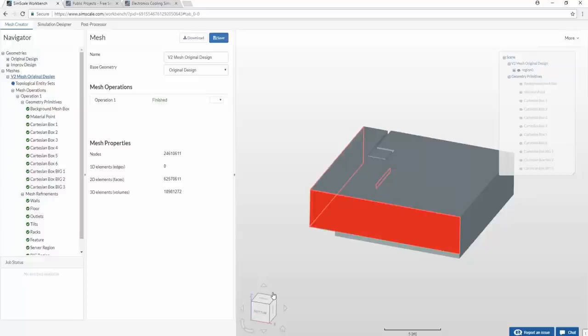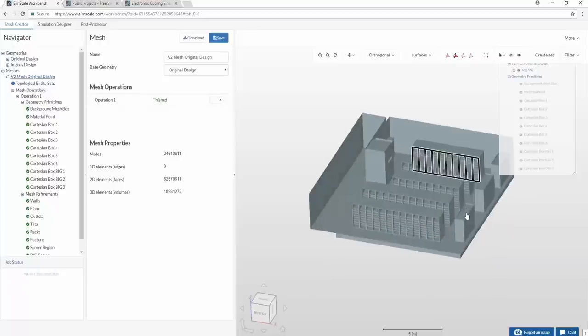At the same time, it's a necessary step in order to have the possibility of simulating the airflow, at least with the methodology that we are applying. So there is no possibility to actually have the CRAC as a functional block. But at the same time, what you could do is have it analyzed and then use it as a black box, where you would assign certain boundary conditions to a given unit. So I would select the suction inlet, I would select the suction outlet, I would select the sides, and I would know what the properties in general of such a device are. So in this sense, yes, but it's not a single click thing.